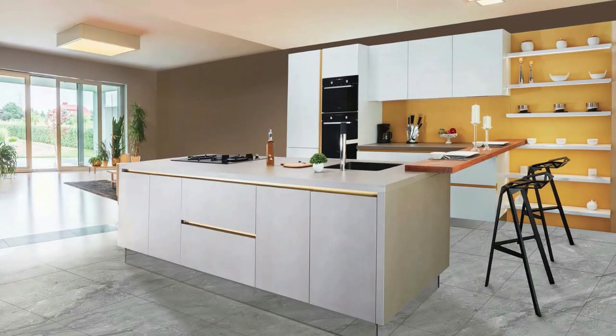So what about kitchens? All kitchens need direct exhaust to the exterior. Some kitchen designs help or hinder removing that exhaust from the highest pollution points in this kitchen, the stovetop and the oven. We've all seen them, professional cooktops stuck in the middle of a vaulted ceiling kitchen with no exterior wall nearby and fully drywalled living space below. A nightmare to ventilate, but that doesn't mean they don't need ventilation. Similarly, giant range hoods need makeup air in order to accommodate for the amount of air they remove from the home when operating.